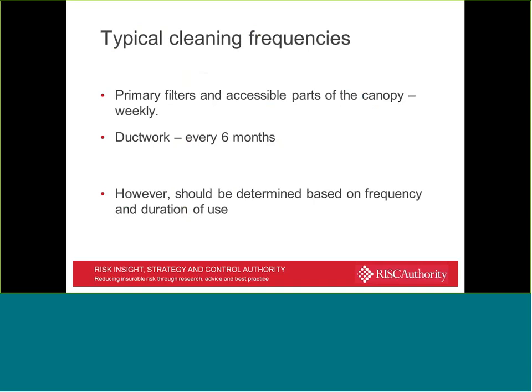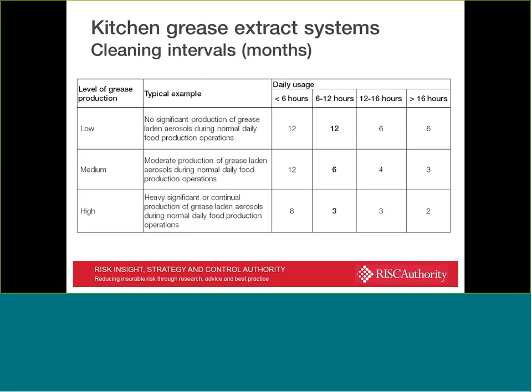So, typical cleaning frequencies, this is what is often put forward: primary filters and accessible parts of the canopy should be done weekly, ductwork every 6 months. A rule of thumb, but it doesn't necessarily fit the bill in the vast majority of circumstances. Frequency should definitely be based upon the frequency of use and the duration of use.